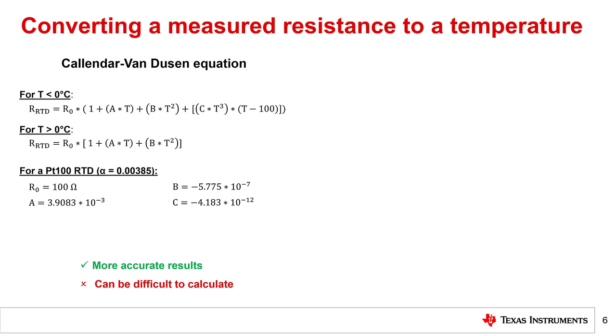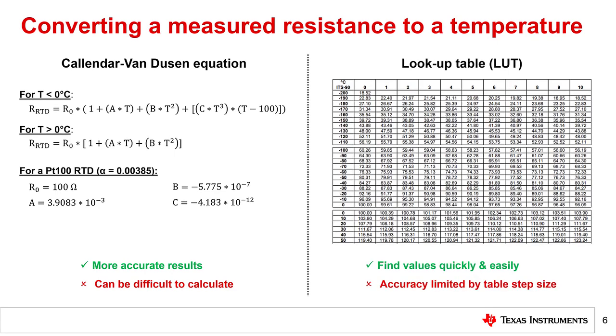Moreover, an RTD system measures a resistance that must be correlated to a temperature, while each of these equations outputs a resistance from the corresponding measured temperature. Therefore, the user must first calculate the inverse of each equation before it is possible to convert the measured resistance to a temperature. The second method to convert a measured resistance to a temperature is a lookup table, or LUT, which is shown on the right. A lookup table uses the aforementioned equations to generate fixed RTD resistance values across a specific temperature range. A lookup table is beneficial because it is a large data set of static values that does not require any computation. The challenge with a lookup table is limited accuracy due to a typical temperature step size of 1 degree Celsius. Identifying temperatures within this standard increment requires an interpolation function, though this is usually a simple computation.